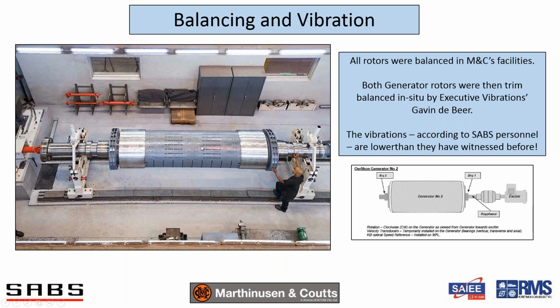Vibration. When we first recommissioned generator 2, it was experiencing something like 17 millimeters per second on the non-drive end axial in plane of the non-drive end bearing. And so what we did is we did some in situ trim balancing by Gavin De Beer. We managed to bring that vibration down by a factor of 3. And Seth and Lucas will comment later, but they were extremely happy with this vibration. They said they haven't seen that low level of vibration before. We also trim balanced Gen 1. All the other machines were balanced at full speed in our facility, and we also did slow speed balancing on Gen 1 and Gen 2 in our balancing machine in Johannesburg.